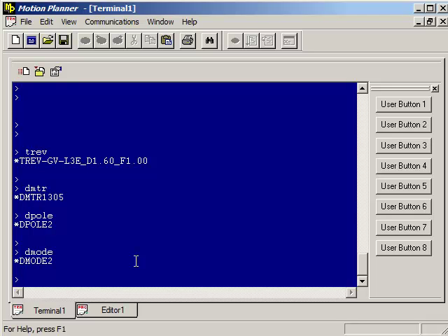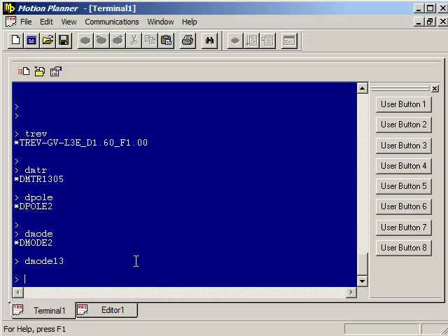The auto run mode is D-mode 13, so D-mode 13, we enter that. The stepper drives would be D-mode 6, which is step and direction mode. So go ahead and type D-mode 13. The drive will be in auto run mode, but you have not connected yet. Go ahead and connect your GC50 or your GEM-VM50 with pins 1 and 2 jumpered. Gonna go ahead and plug mine in.